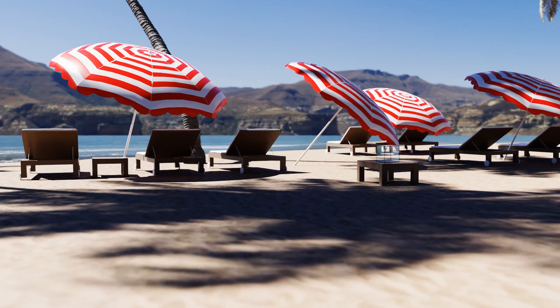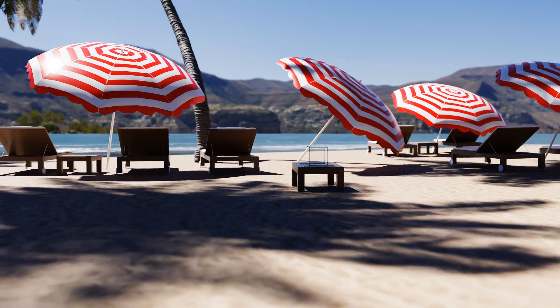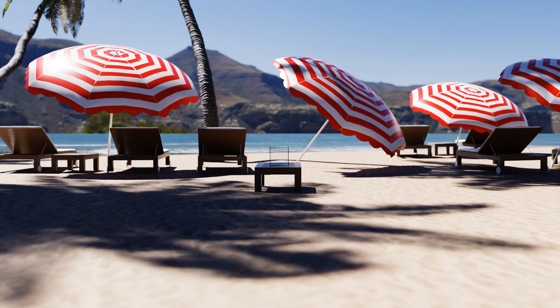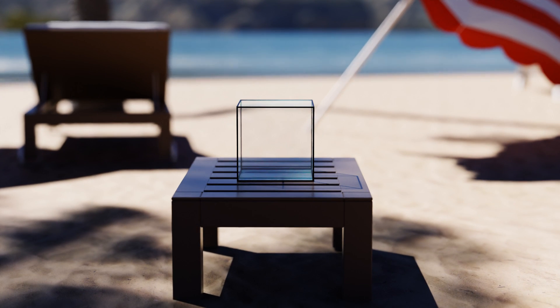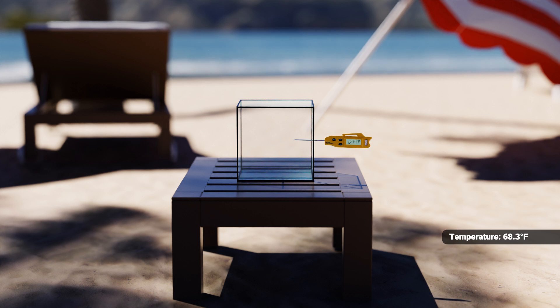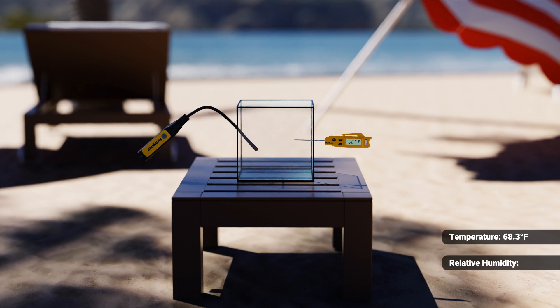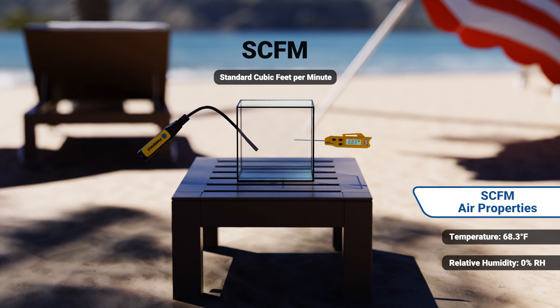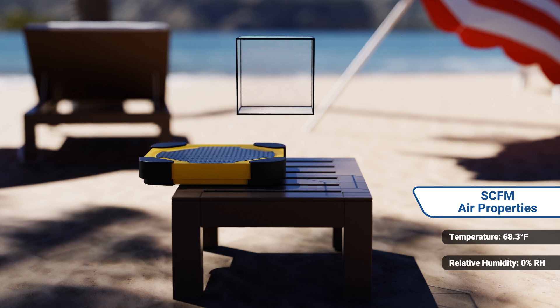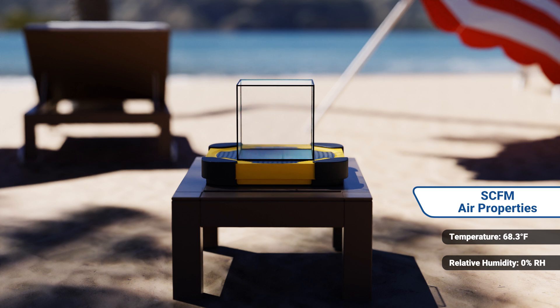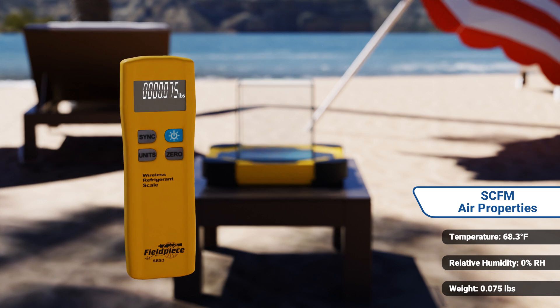To get an idea of the air we're moving, we need to understand the temperature and relative humidity of that air. Here we're showing a box of air at sea level. This particular box of air is 68.3 degrees Fahrenheit and 0% relative humidity. These are the conditions of standard CFM air, or SCFM. Air has weight and takes up space — this box of air weighs 0.075 pounds.